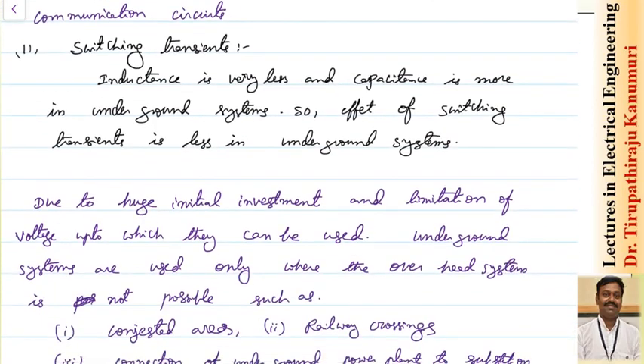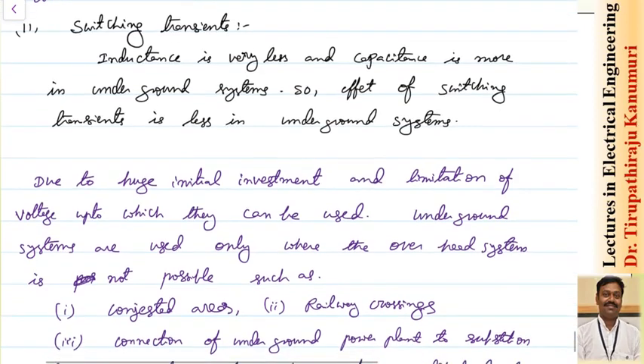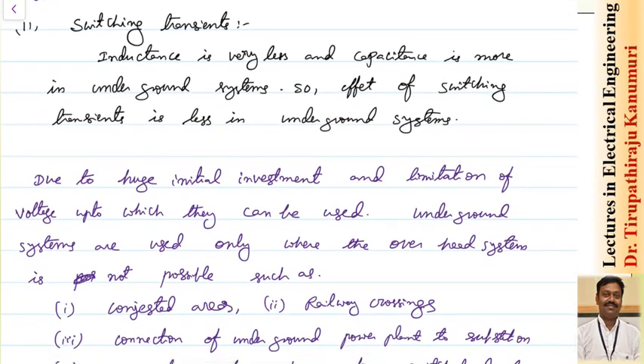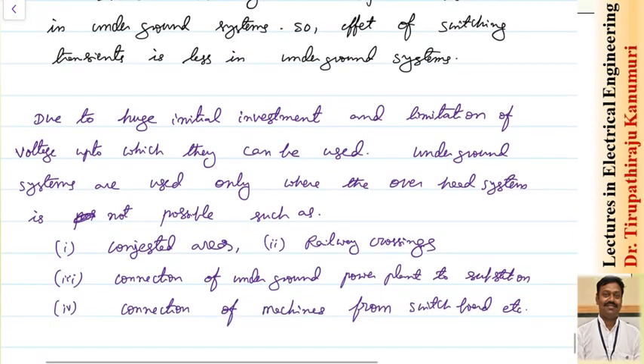Underground systems have minimum interference with communication circuits. Regarding switching transients: when a switch is suddenly closed, the inductor and capacitor oppose the change. Since inductance is very less and capacitance is more in underground systems, the effect of switching transients will be less in underground cables compared to overhead systems.